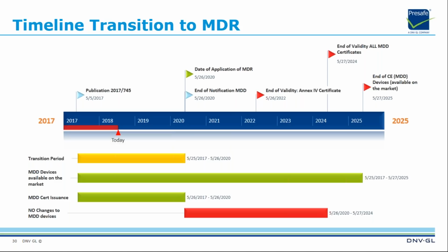End of validity, all medical device directive certificates based on 9342 will be 27th of May 2024. It means after this time, the other certificates which are issued cannot be valid. So the last time validation for certificates based on MDD 9342 will be 27th of May 2024. And end of CE marking based on MDD and devices on the market will be 27th of May 2025. It means all medical devices after 27 May 2025 on the market are certified by MDR, not based on MDD.